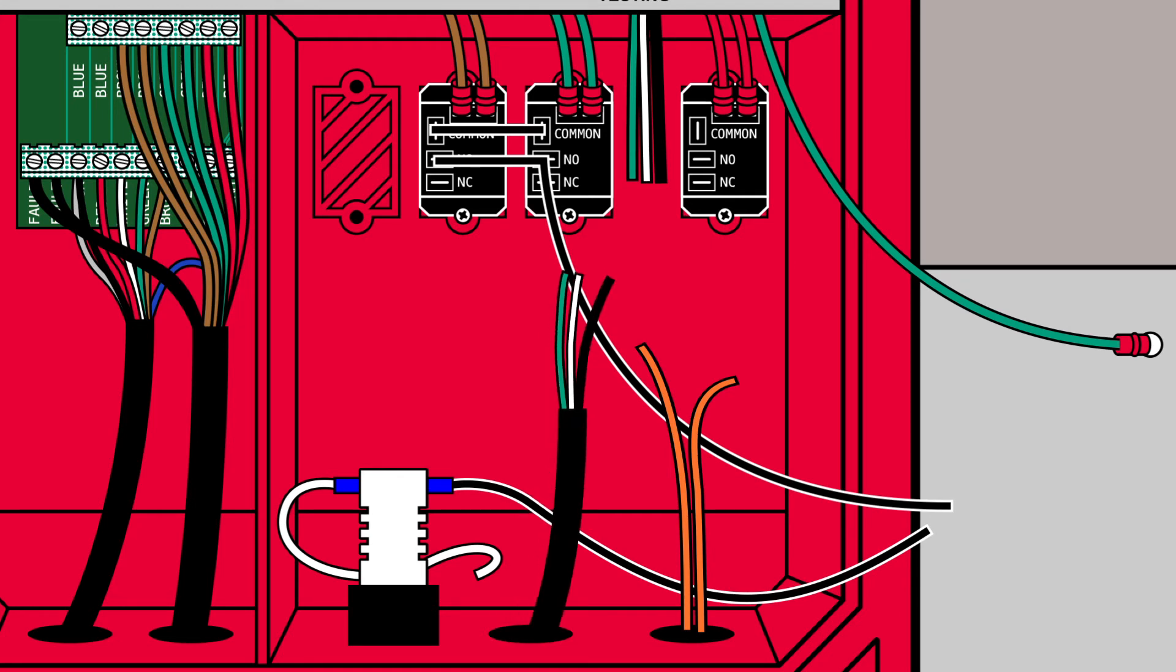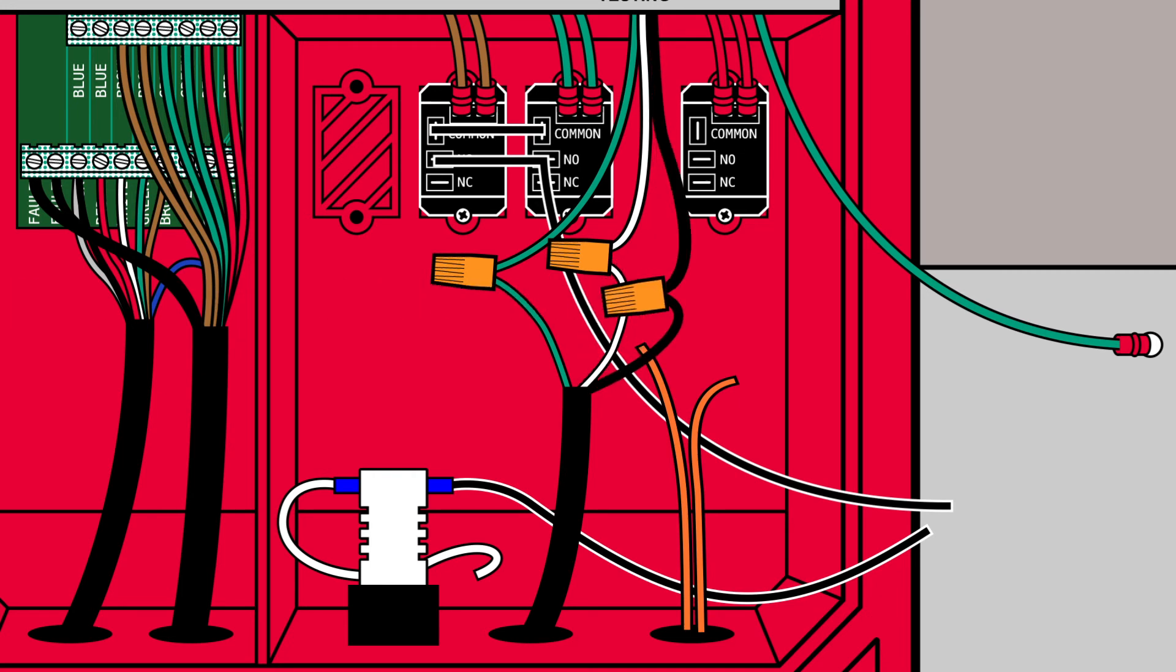Make the power connections. The green wire is ground, the white wire is neutral, and the black wire is the hot wire leg. The audible alarm wires are color-coded to be connected respectively. A jumper runs from the hot leg into the common of the fill relay.